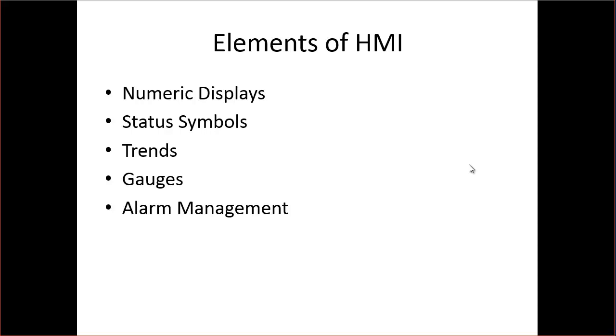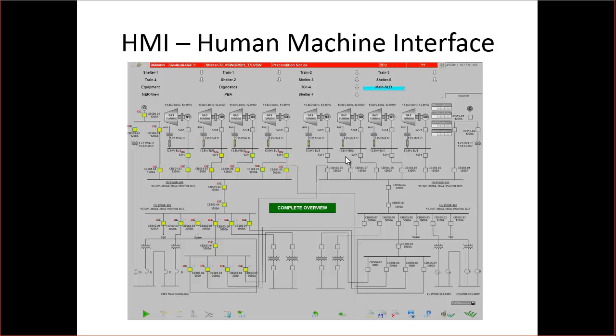The elements of an HMI display include numeric values — things like your voltages and currents. There are also status symbols indicating whether a switch is open or closed, a breaker is open or closed, or a generator is operating. You can see numeric displays right here with values being read and displayed on the screen. The status symbols are all these symbols on here, and it's common for these to be animated — you can see breakers open and close, or colors change to indicate whether they're open or closed.